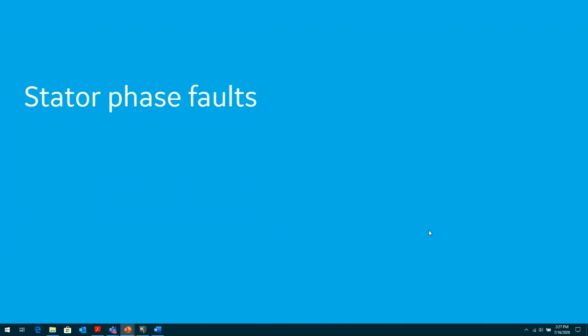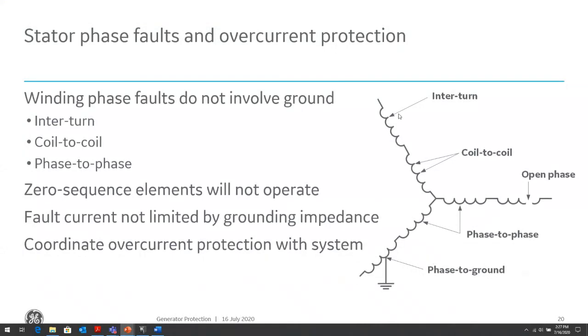So let's focus first on how we protect for phase faults within the stator. Within the stators, there are different types of fault. There can be interturn faults between the various coils within the generator, and then we can have coil-to-coil faults within the same winding of the generator. Then we can have phase-to-phase faults between the various windings of the generator. The commonality within all these faults is that we're not going to see ground fault current. We're not going to see zero sequence elements, so with any type of ground fault, zero sequence protection, chances are we might not be able to pick those up. So we need to be able to protect against these phase faults and be able to coordinate for phase faults outside the generator zone within our power system.